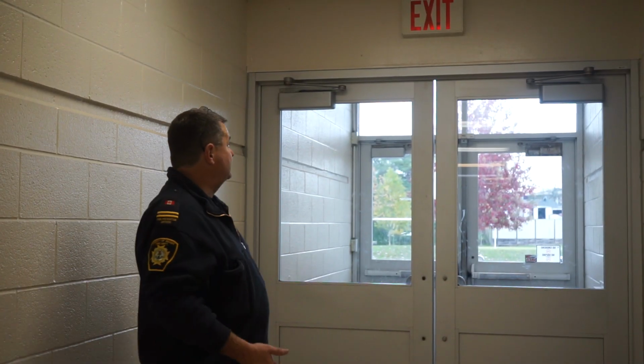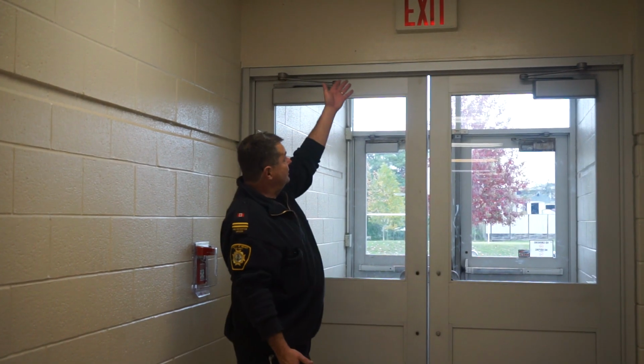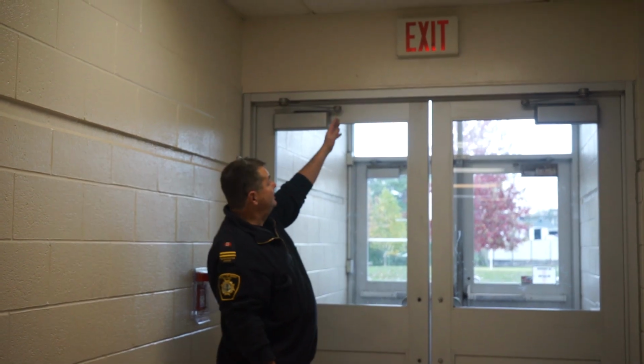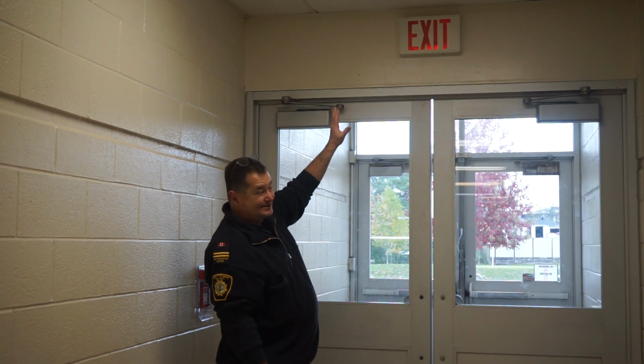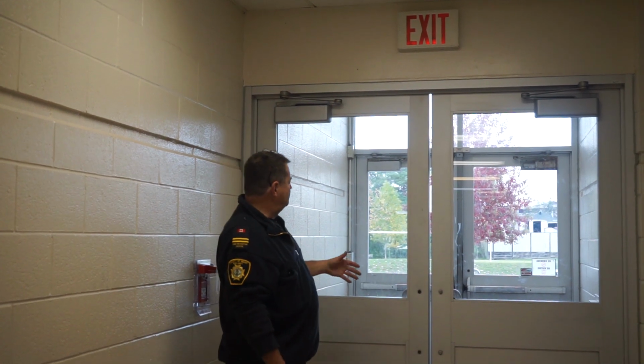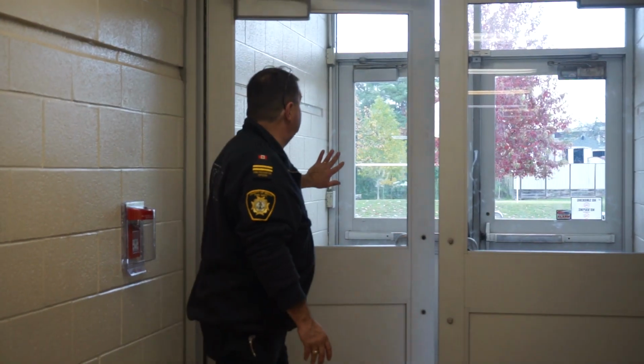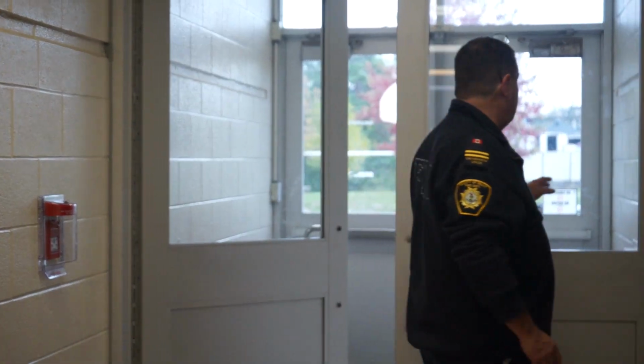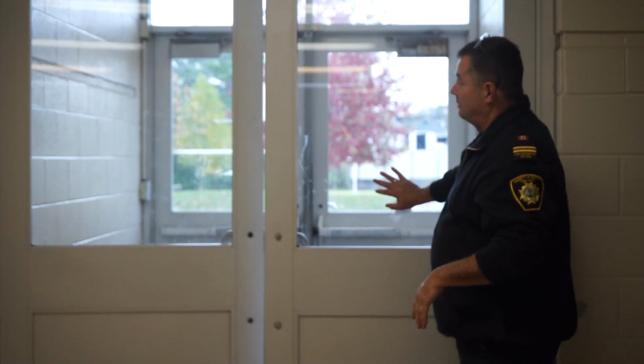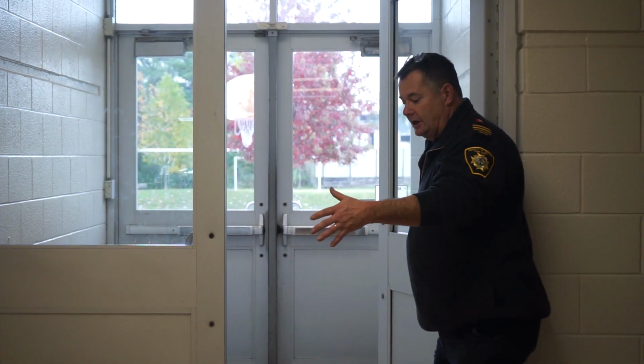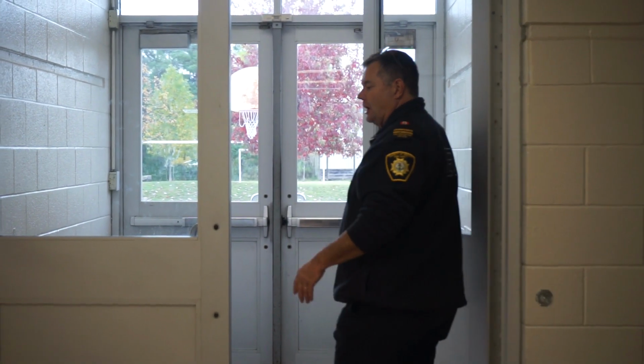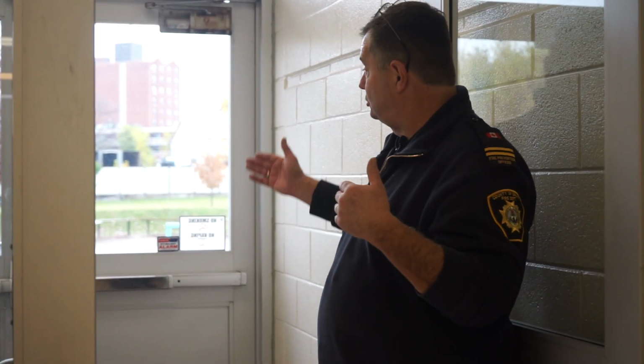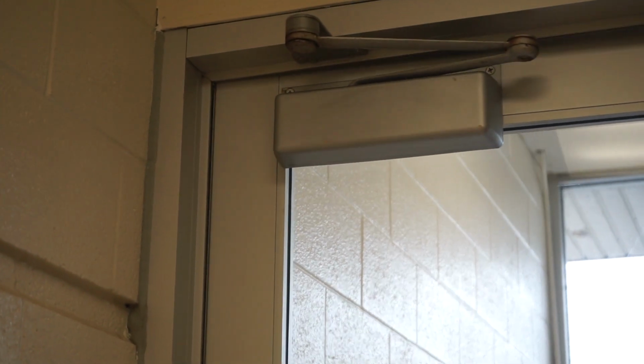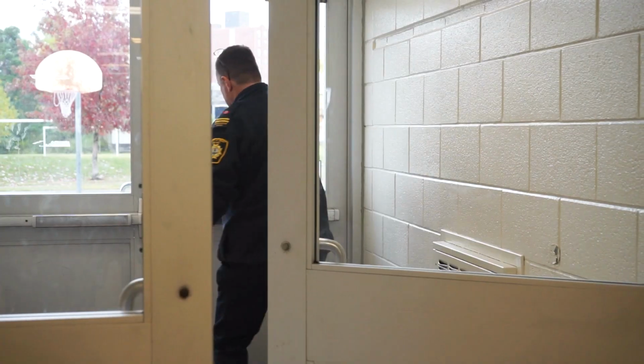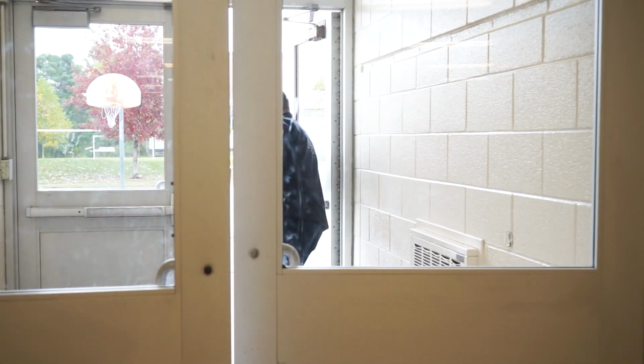When we inspect a building, we absolutely make sure that all of our exit signage is in place, meaning it's there, it's functioning, it's not damaged in any way, and as well, our exit doors. We want to make sure that all of our exit doors not only operate, but they're not blocked, they're not inhibited in any way. And I'm just going to walk through and we're just going to check the two exterior doors, because these doors are equipped with what's called an automatic closer. With this, we're just checking the exterior doors.